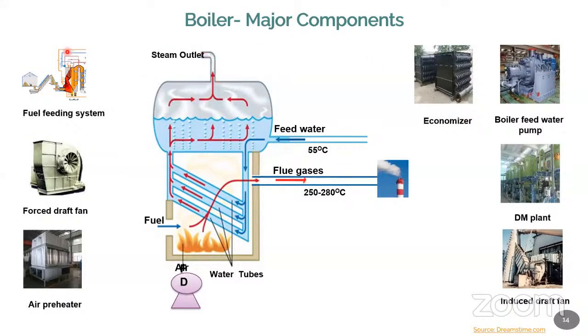Now you let out the steam and that will be going to the process. Now the steam will have a very high energy content. Now it is in the gaseous state. The piping system for carrying the steam should be properly insulated. It should be very, very well insulated. So the outer temperature of the pipe should be almost equal to your ambient temperature. Practically it's not possible, but it may be around 30 to 40 degrees, maybe higher. Very correctly speaking, it should be 20 to 30 degrees higher than your ambient temperature.